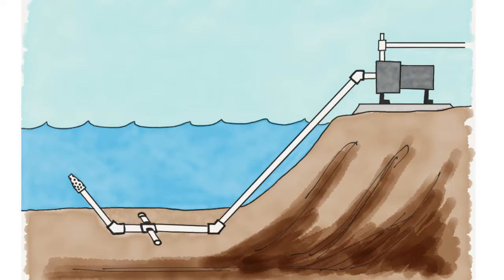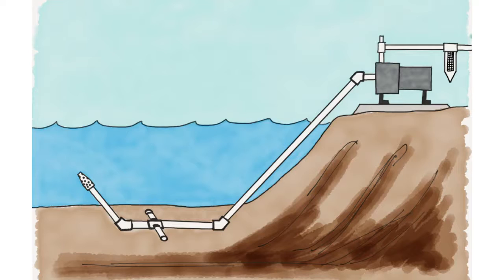Now, if you're pulling from a lake or a canal or some type of body of water that may be a little bit dirty. And in fact, centrifugal pumps on the edge of a lake, they're basically pulling from the bottom of the lake. They may have a pipe that goes along the bottom and angles up a few feet off the bottom, but even still, it pulls water up and it pulls these particles up from the bottom of the lake. So in those situations, if I'm installing that type of system, what I'm going to use is maybe two layers of filtration, a large filter on the main line as the water comes out of the lake. And then once it gets out to the individual zones, I use a smaller filter to make sure we screen out the small particles from that.